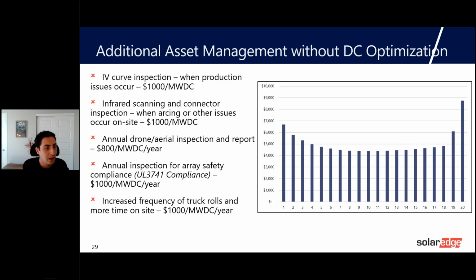Drone inspection is something we've heard is typically done annually for this kind of system, an annual inspection for array safety compliance. To maintain compliance with the standard, given wear and tear and aging of mechanical components, if we want the system to still provide benefit to firefighters, frequent inspections for robustness of these mechanical protective devices should be done. This is another operations cost that we are expecting for systems that are using non-DC optimized solutions. And finally, without the granular monitoring data that you get from each optimizer in your field on the rooftop, it would be more likely to require truck rolls when investigating issues in the array. And there's more time spent on site finding those issues because you don't know down to the module level exactly where an issue has occurred.